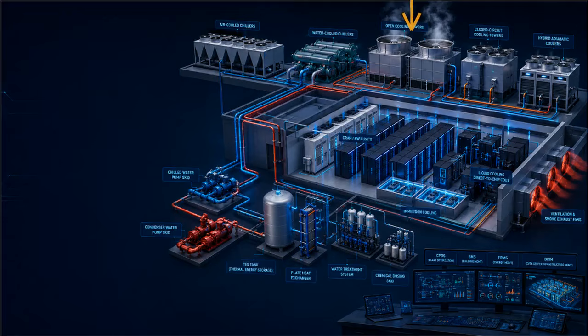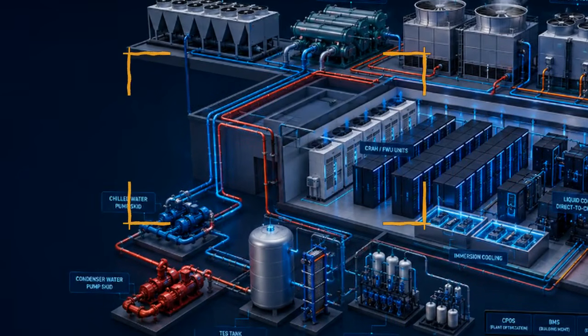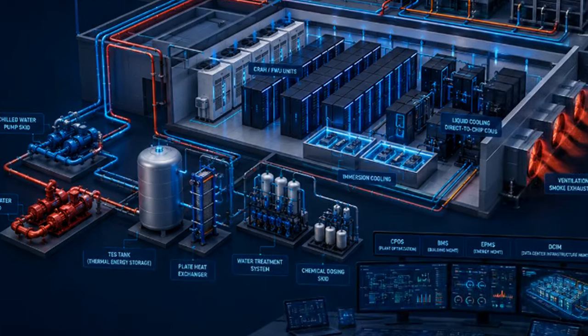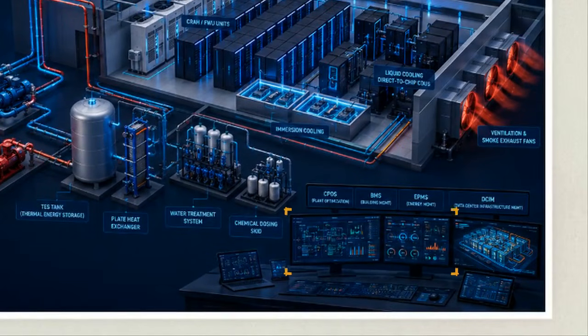We track thermal transfer from the IT load to the atmosphere by isolating specific loops: the server air loop, the chilled water loop, and the condenser water loop. Every point is governed by strict control boundaries. Local controllers dictate safeties, while the central system coordinates operations.